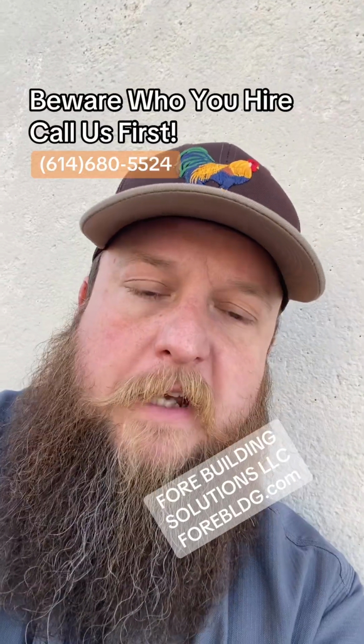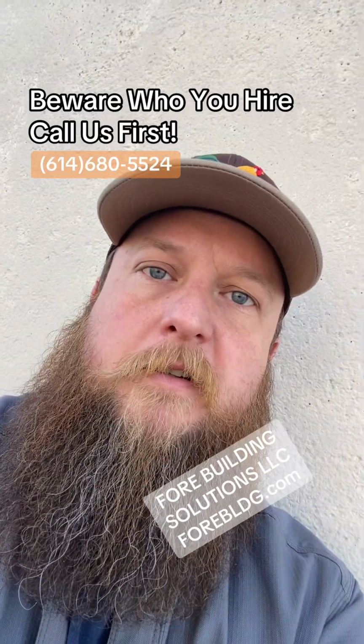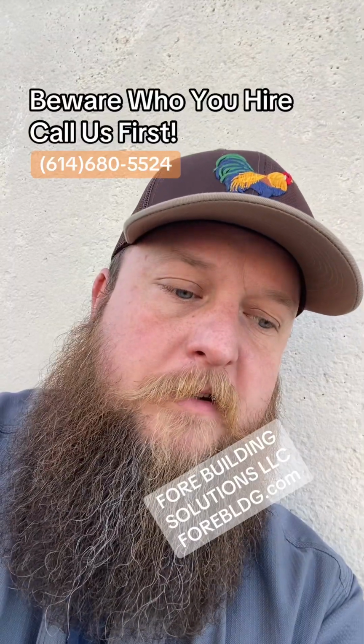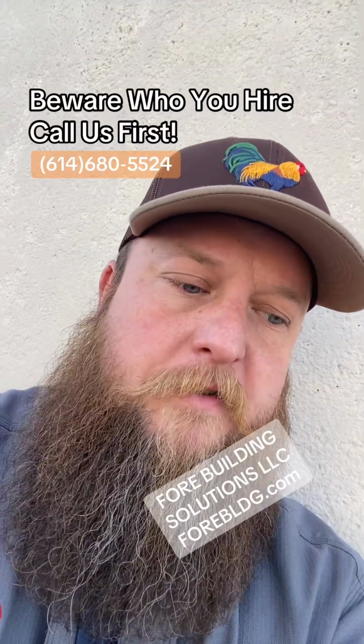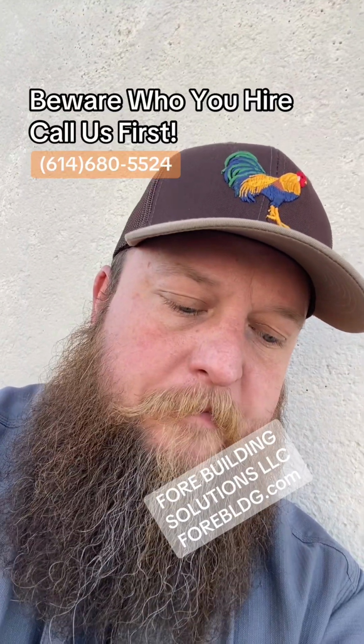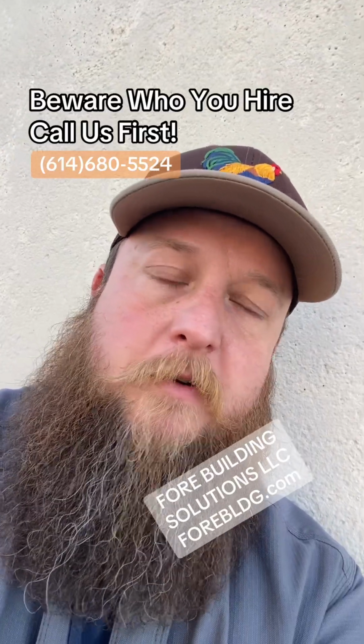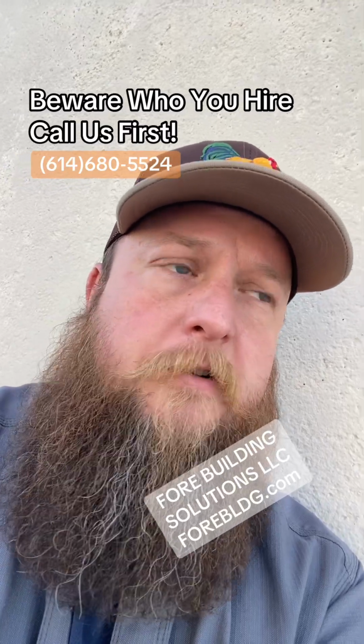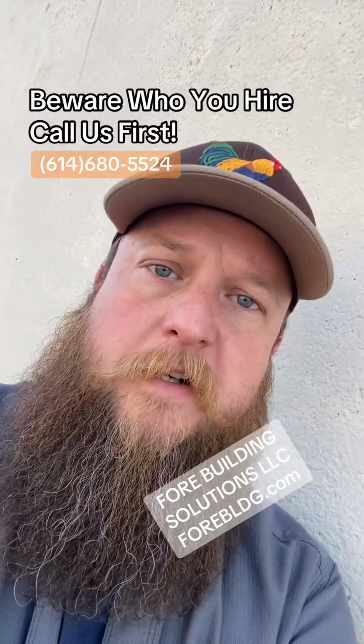So I said, sure, I'll go look at it. I get out there, the gentleman shows me the pictures that the contractor gave him. They're very fuzzy pictures. I saw no cracks, but saw a little bit of rust, which could be pinholes, could be a problem. So I went ahead, took a look at it. I found no serious damage, just a little bit of wear and tear, just a little bit of rust. That's normal. There were no cracks, there were no holes. But to verify, I did a combustion analysis.